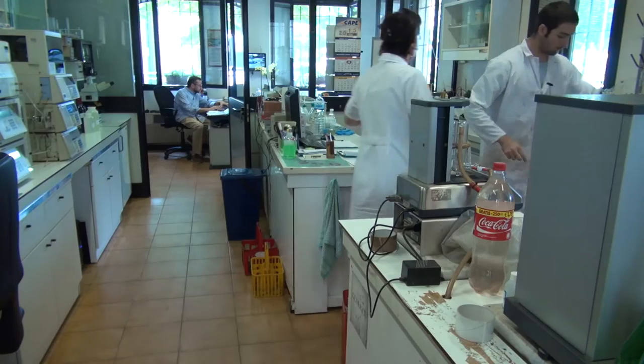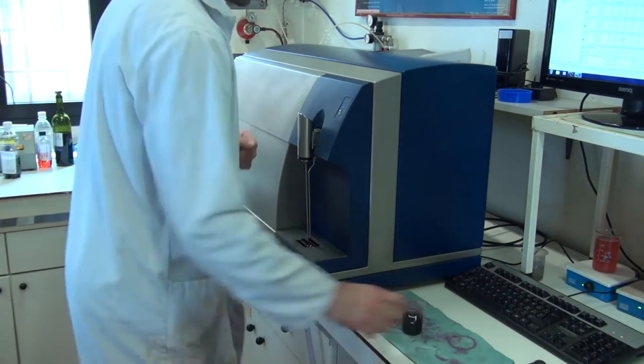This time usually reached up to 20 to 25 minutes per sample. For this reason, we just switched to the third configuration — the SO2 FLEX scan — because we needed a very fast way to know the exact amount of SO2 in our products. We perform about 150 analyses per day, so it's a very useful machine.